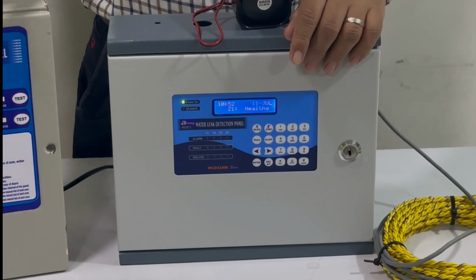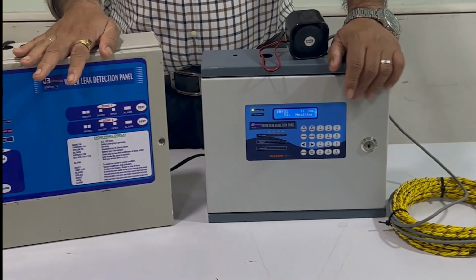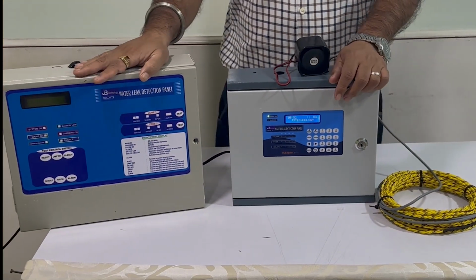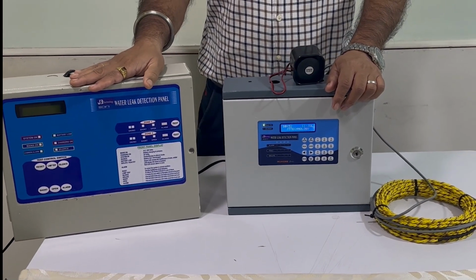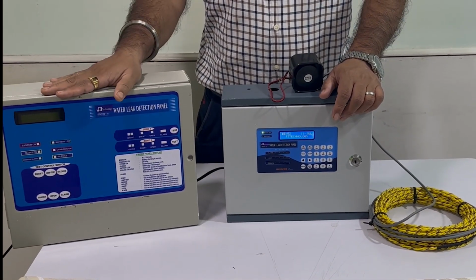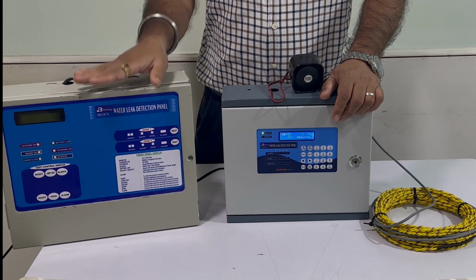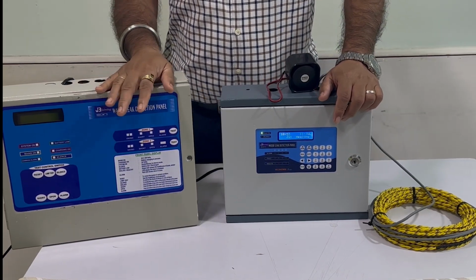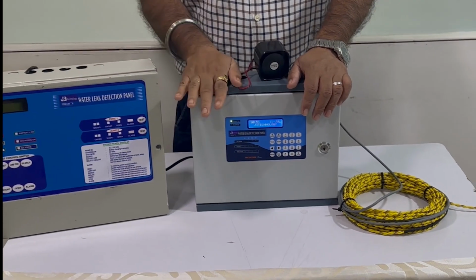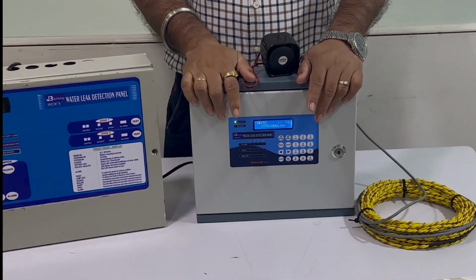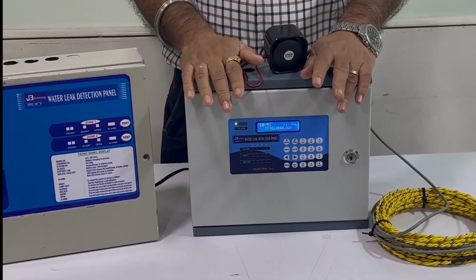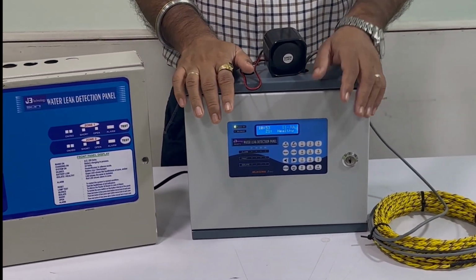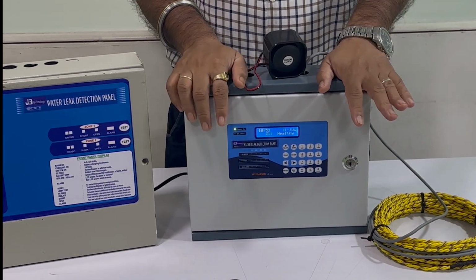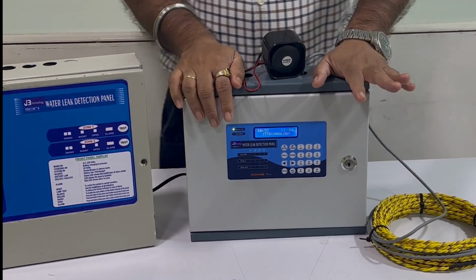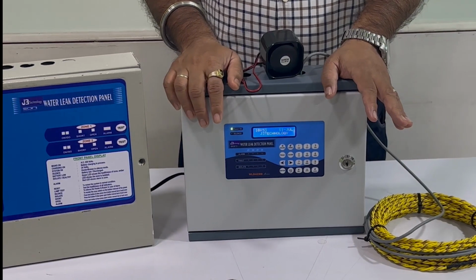In our old panel, for the BMS system, you get dry contacts. You can only take the dry contacts from each individual zone to the BMS panel. In our new launch panel, you get an individual dry contact for each zone, as well as the Modbus facility, which can be connected to the BMS with two wires.